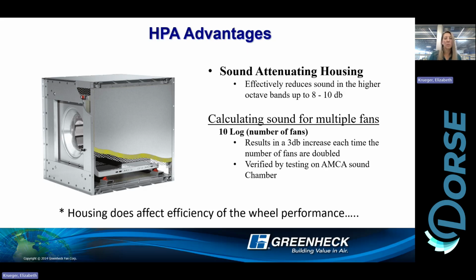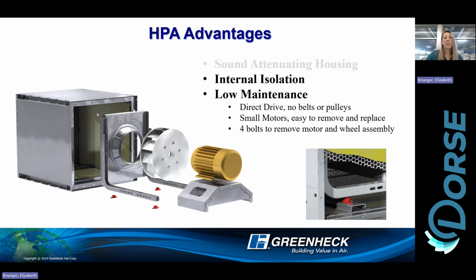When you talk about decibel levels, if it's anywhere less than 3, you won't even notice. 3 decibels actually means, as it kind of explains here, that the sound from a number of fans would be doubled if you didn't have that 3 decibel decrease. And I talked about internal isolation with these as well. Isolating a fan means that you are stopping the vibration from becoming a sound elsewhere in the building, right?